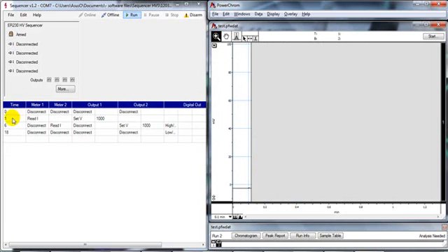I've made a sequence here which starts at 1 second, which is the injection step. The step starting at 6 seconds is the separation, and this is where I set the digital output to high. When it finishes, it's set to low. So this controls the digital output at the back of the high voltage sequencer.